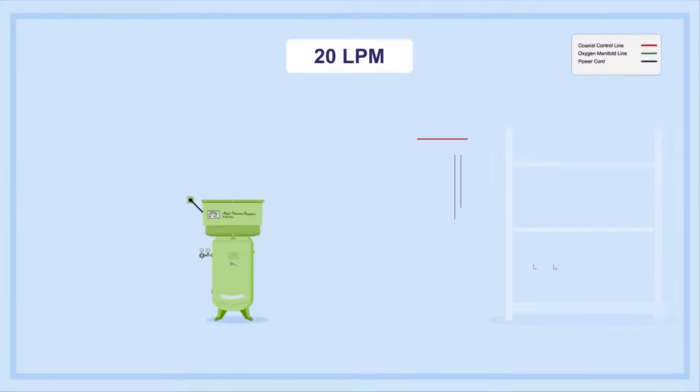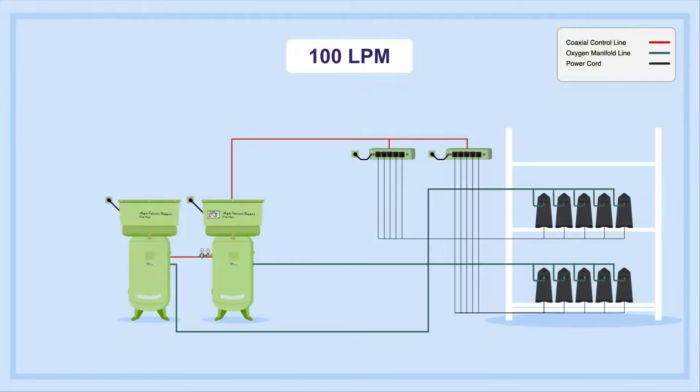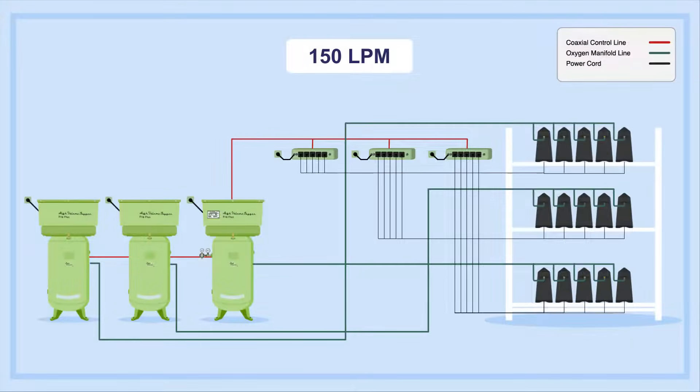HVO systems are modular and expandable up to 200 or more liters per minute. Using multiple oxygen concentrators ensures that the loss of a single concentrator doesn't stop oxygen generation. In addition, you can add components to build a large-scale system with multiple points of redundancy to keep your system running.